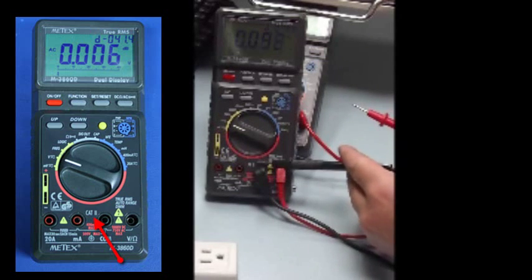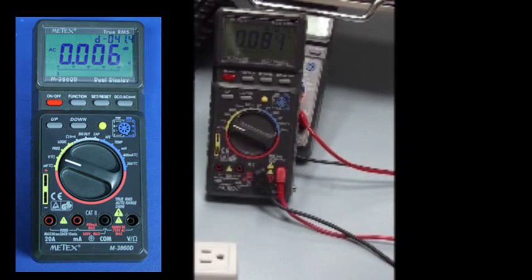So for example, you see that this is a Category 2 multimeter. And in essence, that means we can go up to about 480 volts AC. Yes, the rating is 600 volts, but due to some factors, we really don't want to go much beyond that.